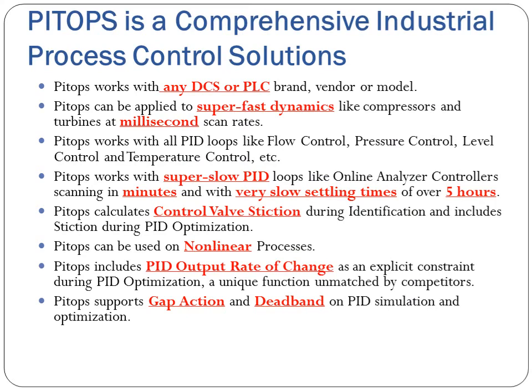PITOPS works with any DCS or PLC brand, vendor, or model. It can be applied to super-fast dynamics like compressors and turbines at millisecond scan rates, and works with all PID loops — flow control, pressure control, level control, temperature control, etc. PITOPS also works with super-slow PID loops like online analyzer controllers scanning in minutes, with very slow settling times of over 5 hours. It calculates control valve stiction during identification and includes stiction during PID optimization. PITOPS can be used on non-linear processes and includes PID output rate of change as an explicit constraint during PID optimization — a unique function unmatched by competitors. It also supports gap action and deadband PID simulation and optimization.